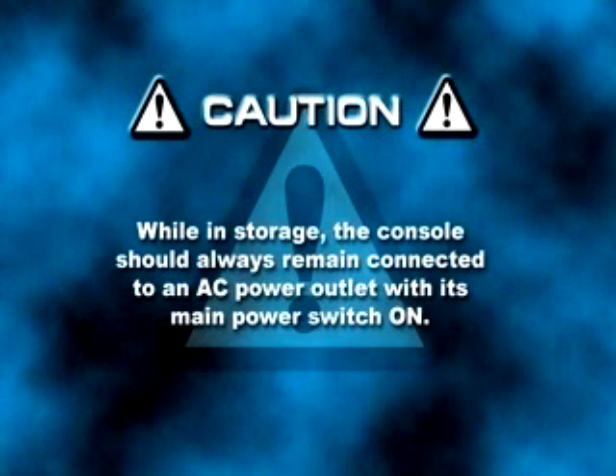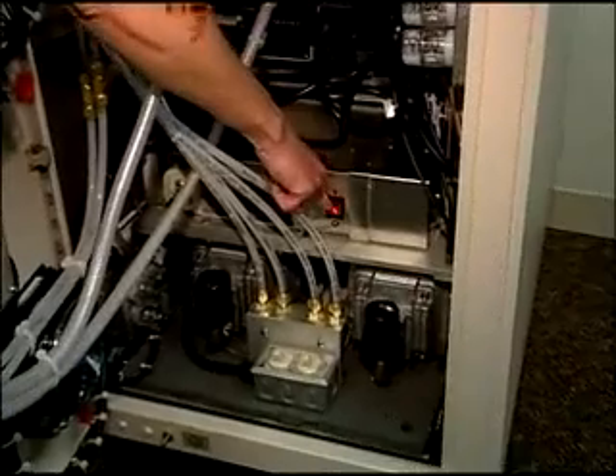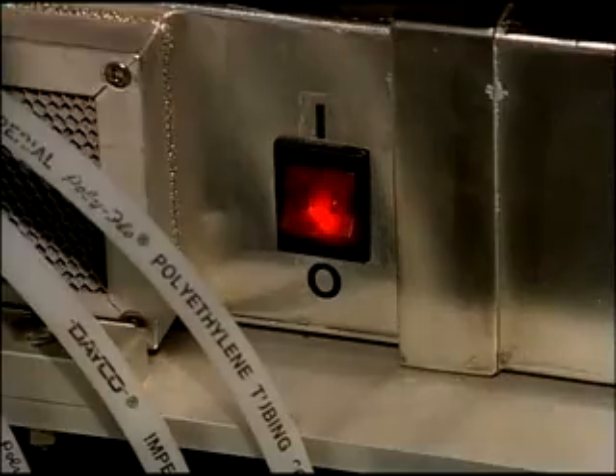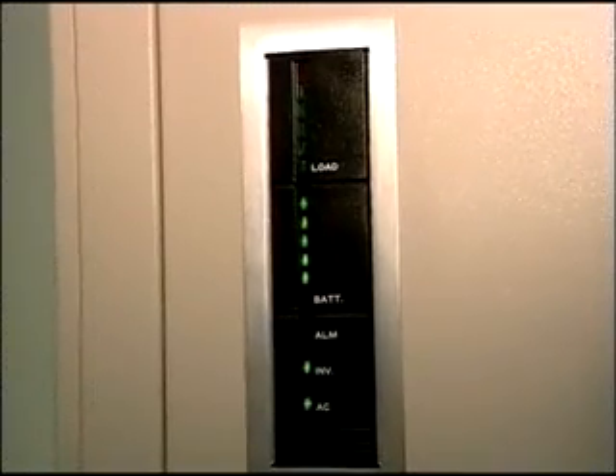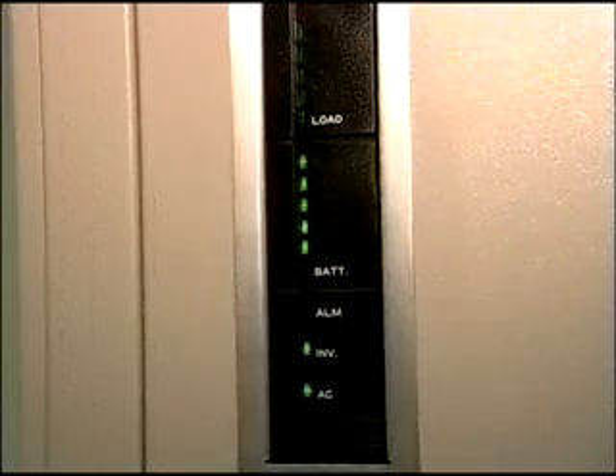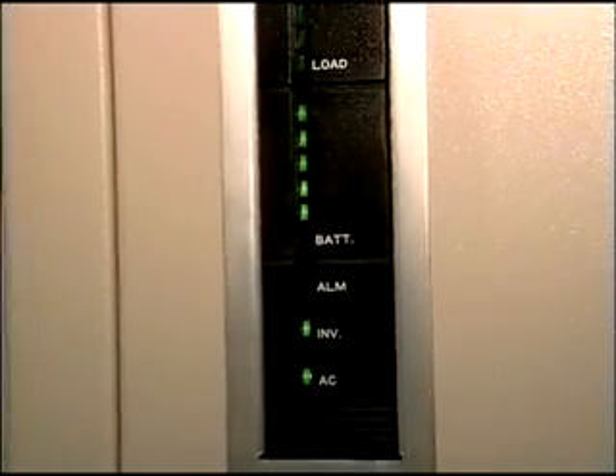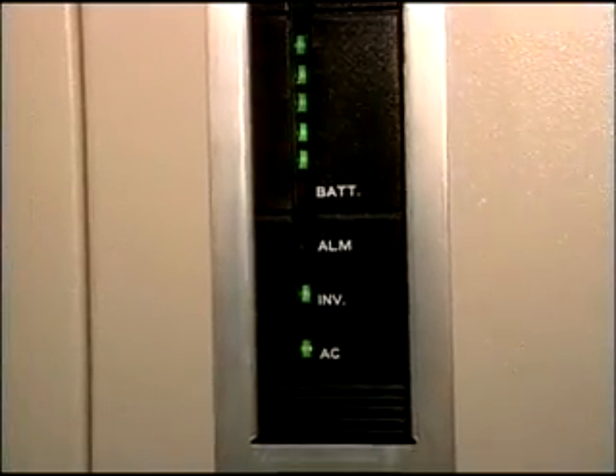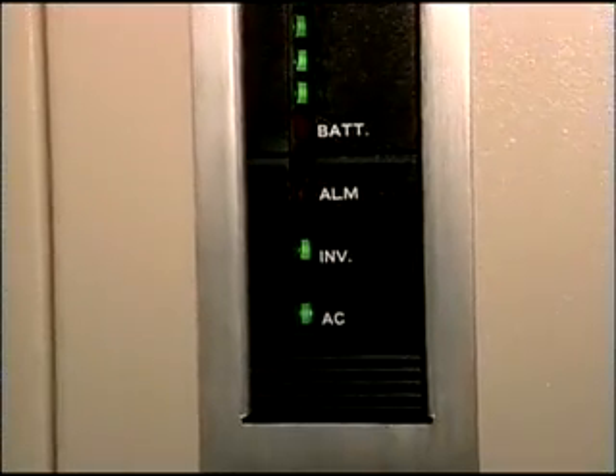Before the dual drive console is used to drive the pumps during surgery, it must be set up and calibrated. While in storage, the console should always remain connected to an AC power outlet with its main power switch on. Check that the power switch for the uninterruptible power supply, the UPS, which provides battery power to the console, is also on. The status panel on the front of the console should read, "Load, no lights. Battery, 1 to 5 green lights on. Alarm, off. Inverter, on. AC, on."